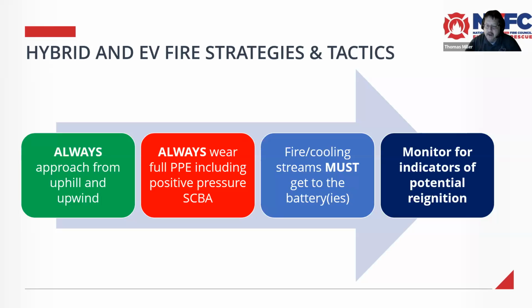Run that thermal imaging camera over it. Make sure you're cooling the batteries, and make sure you're seeing temperature differentials. Every time you hit it with water and do a pan, you should notice temperature drops of between 60 and 150 degrees. That tells you if you're being effective.